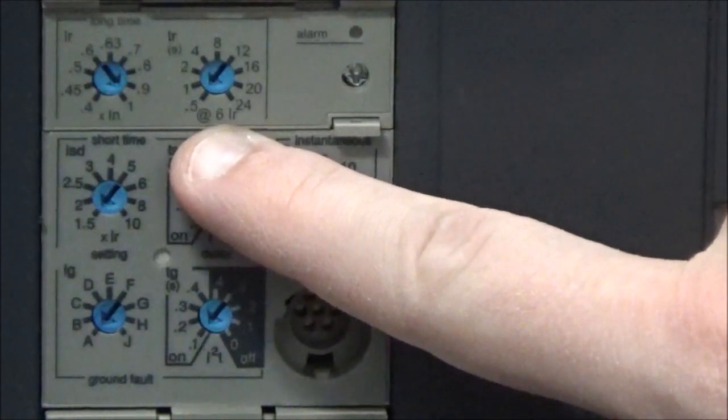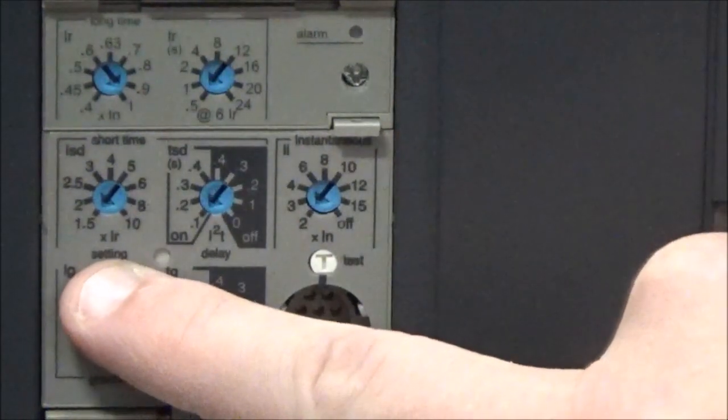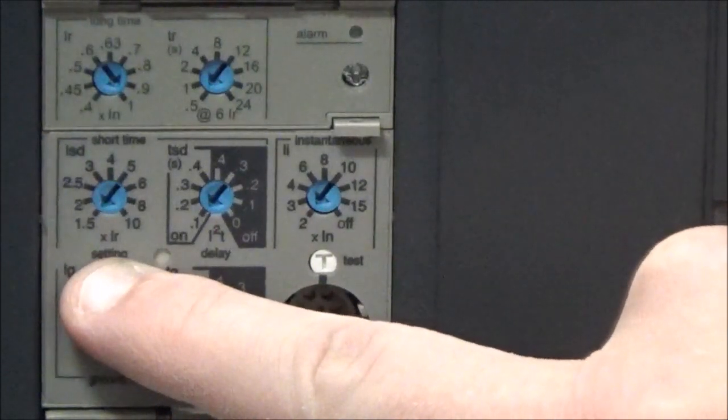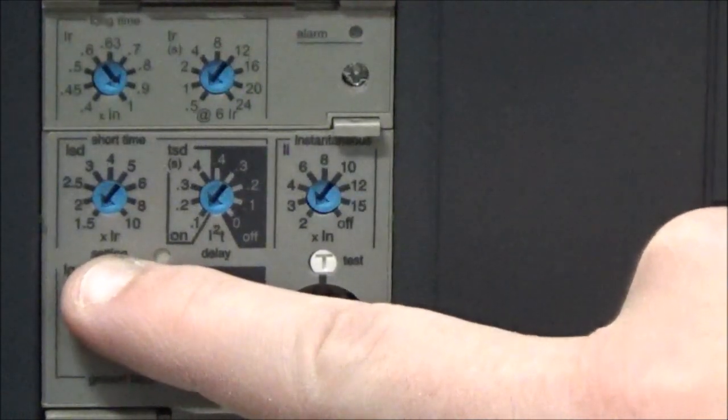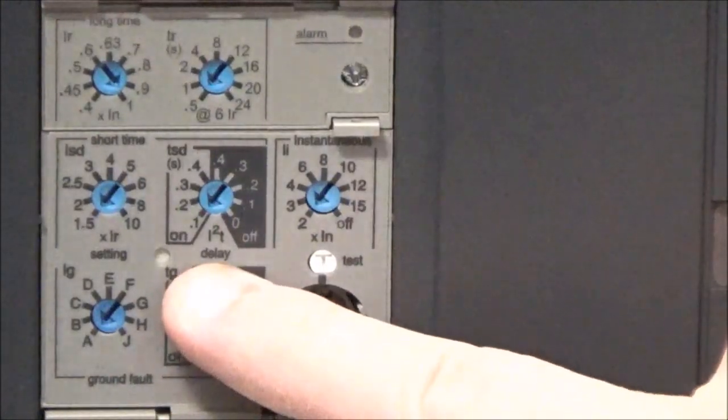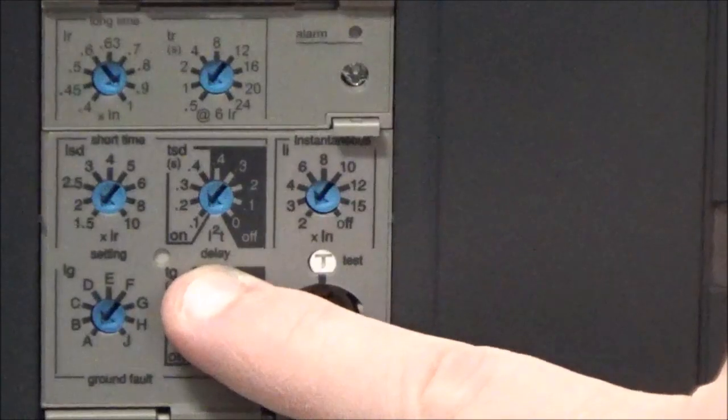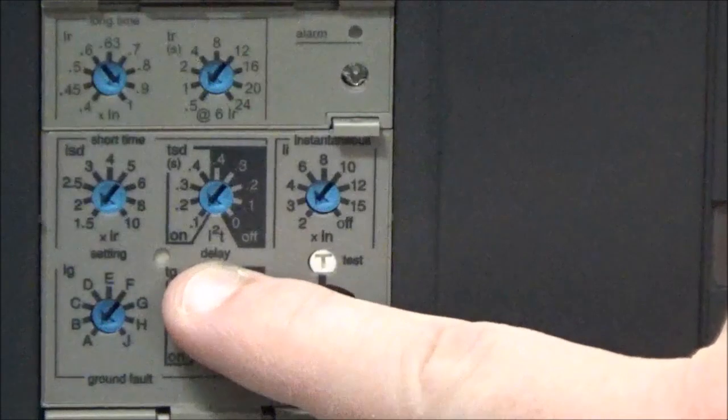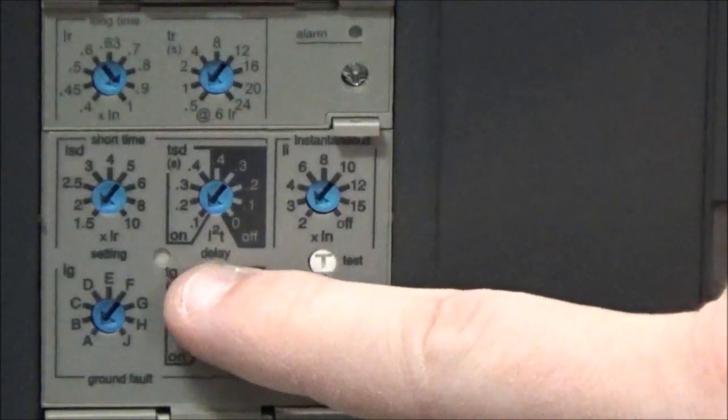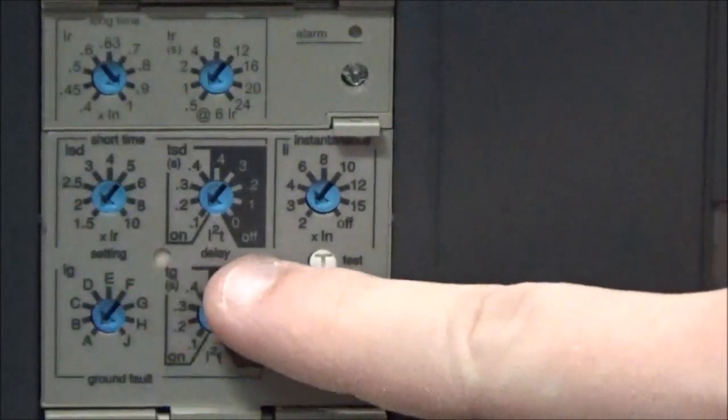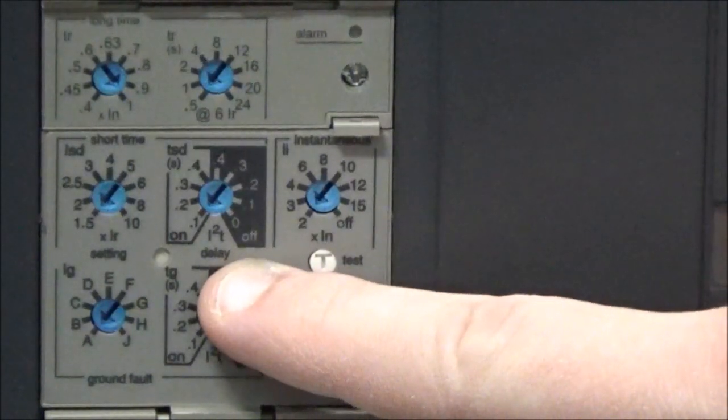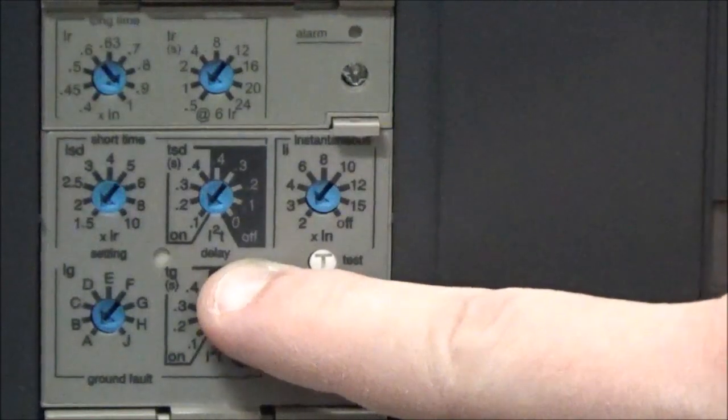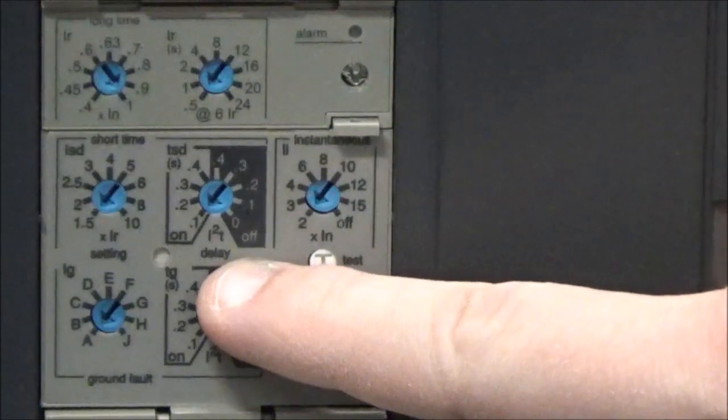You will also have the TSD dial, which is the short time delay setting. The settings on this are given in seconds as well, and you will notice that there are two sides to it: the non-shaded on side and the shaded off side. These are for the purpose of zone selective interlocking. If you are using zone selective interlocking you would use the shaded off side, and if you are not using zone selective interlocking you would use the non-shaded on side.